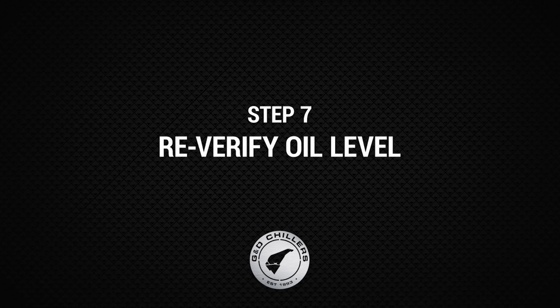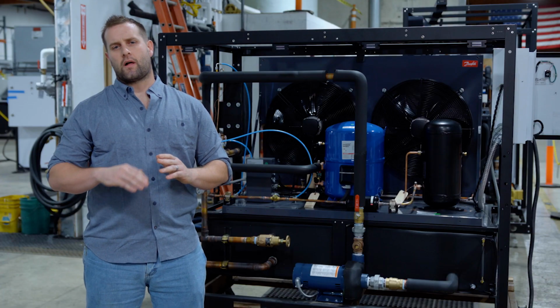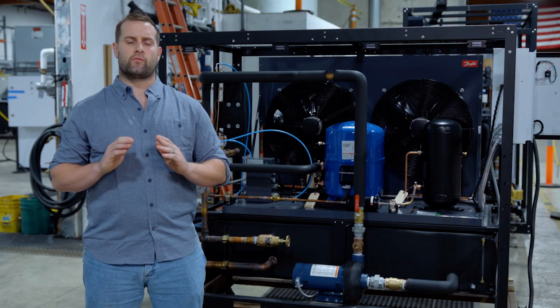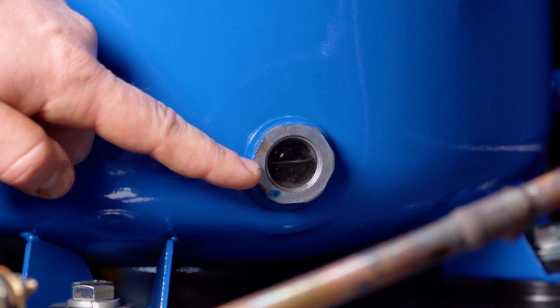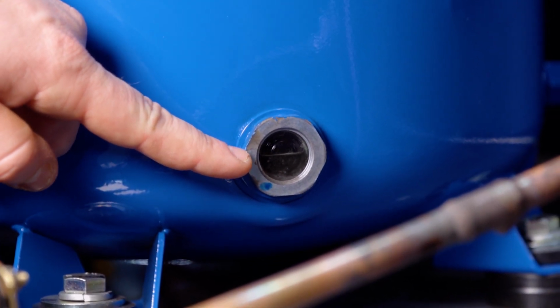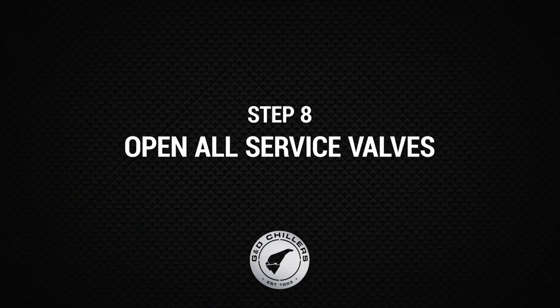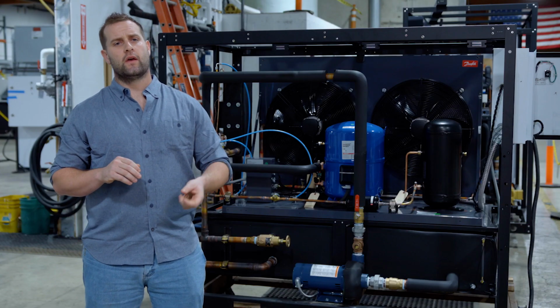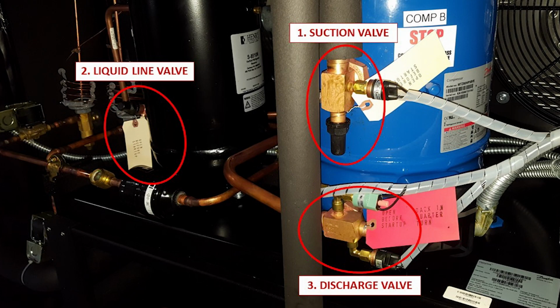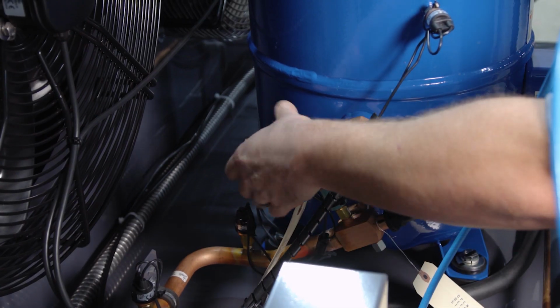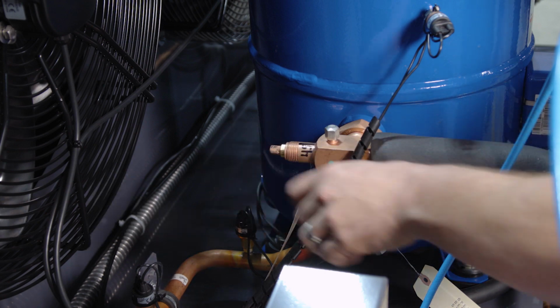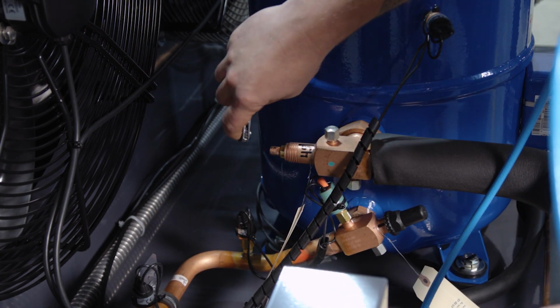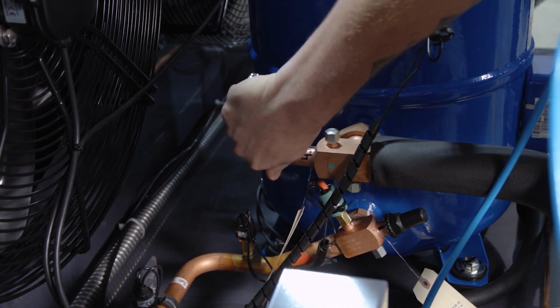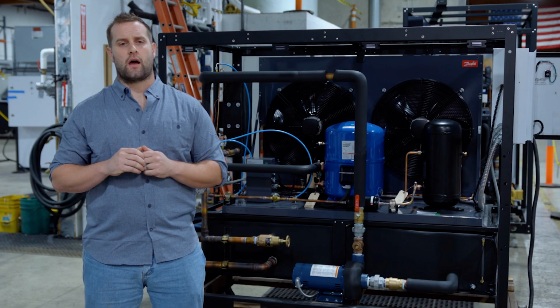The next step on the startup, after you flush and fill with glycol, you're going to go to your compressors and re-verify the oil levels. You want to check to make sure you still see that line, and you're going to go ahead and open all your service valves. On a single stage chiller like this, you're going to have a suction and discharge service valve on the compressor, and you're going to have a service valve on the receiver. All three of those need to be opened up all the way before proceeding. This is a step in the startup that if it's not done right can cause issues, so please make sure you open the valves correctly. If you have any questions, just call into the office, we can help you out.